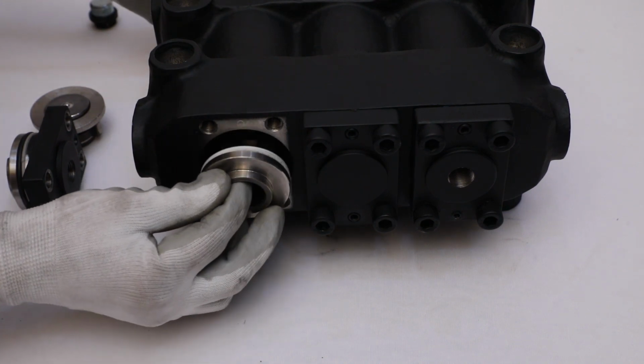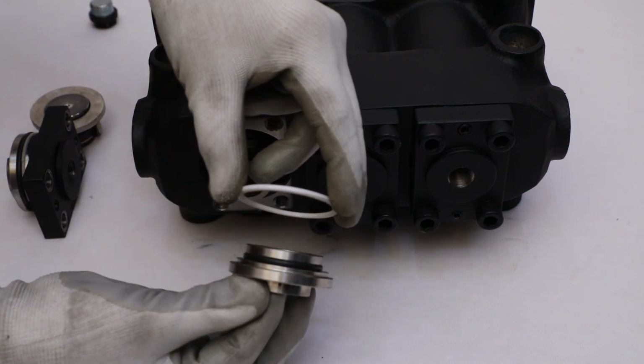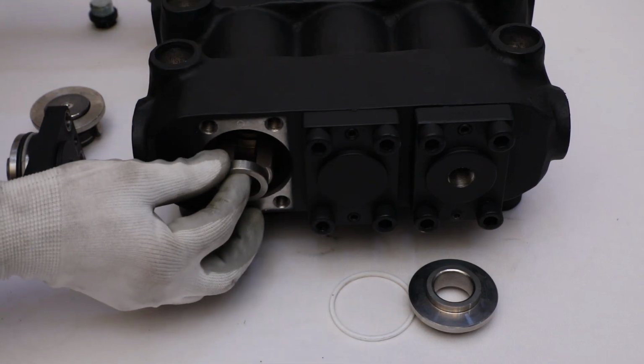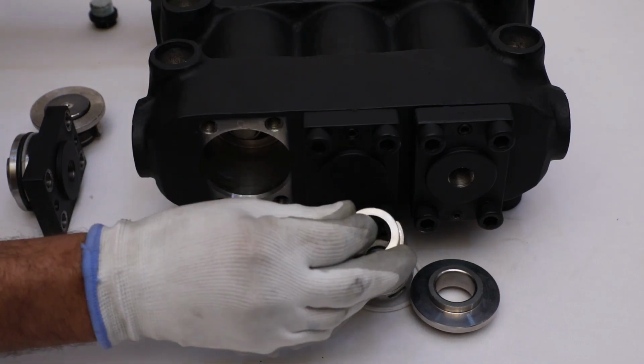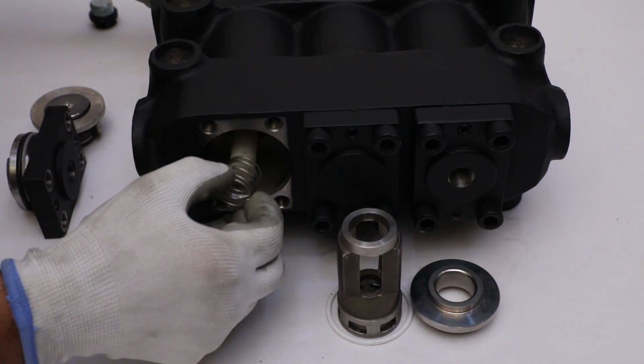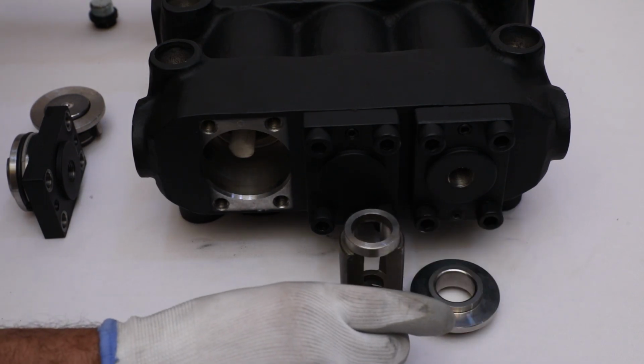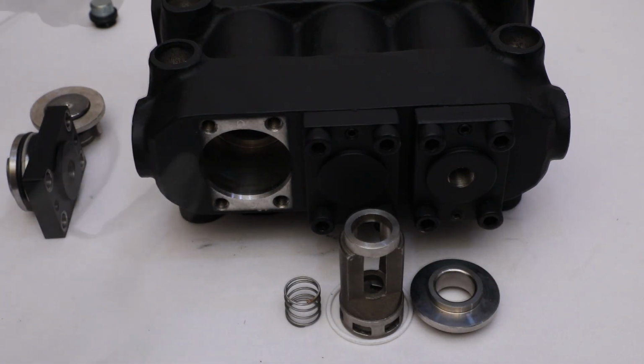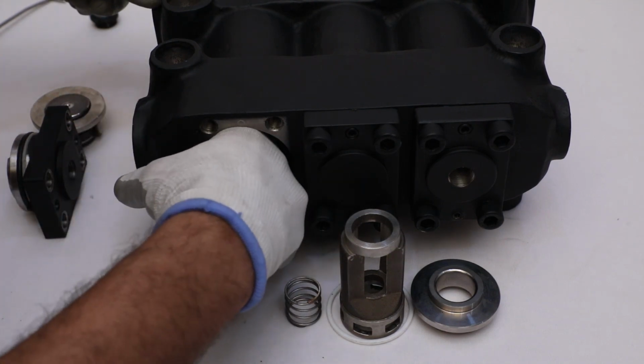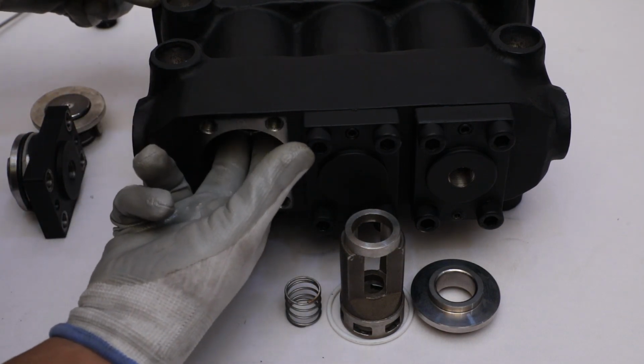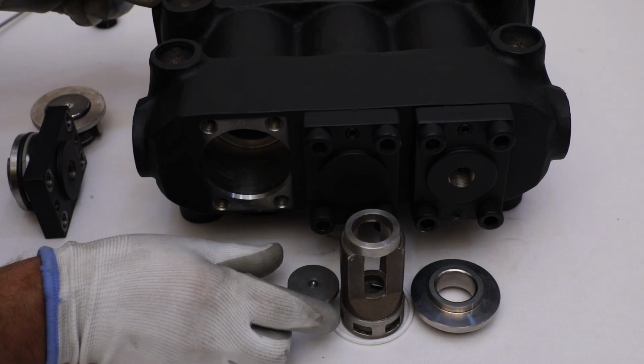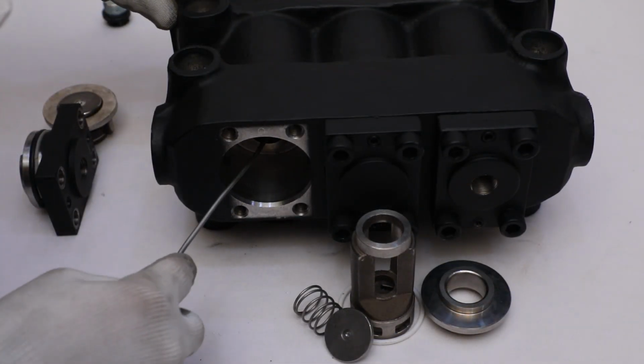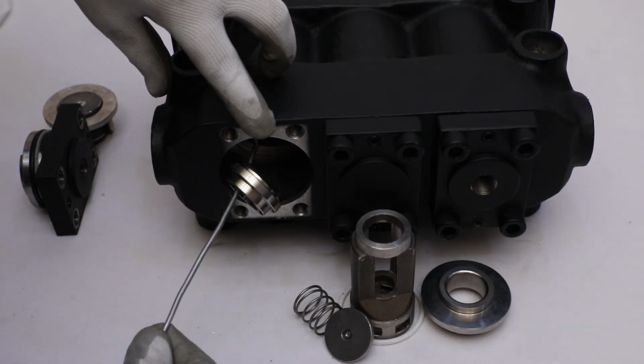Now, take out discharge valve seat, PTFE gasket, suction valve seat guide, helical spring, suction and discharge valve plate by pushing nylon rod. With the help of a pick, take out suction valve seat and O-ring.